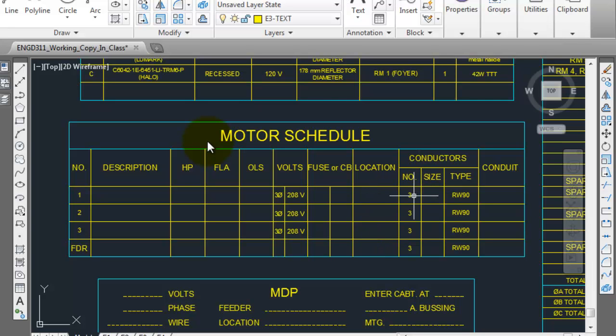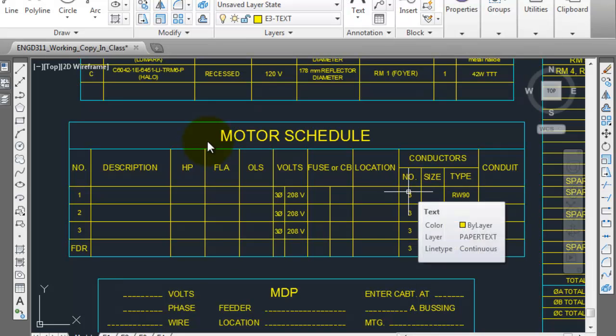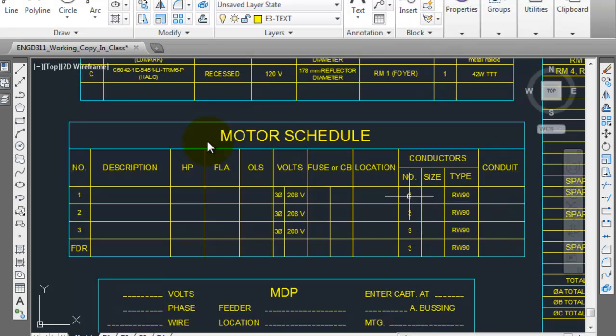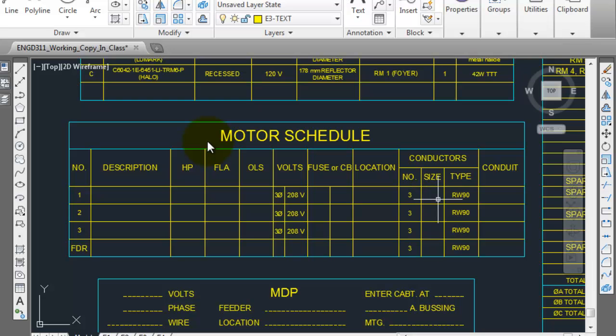The conductors, we have three conductors for a three phase motor because it is a balanced load. It does not require a neutral, therefore you only need three conductors. And this is going to be the size of those conductors. So this is going to be the American Wire Gauge size that you determine.